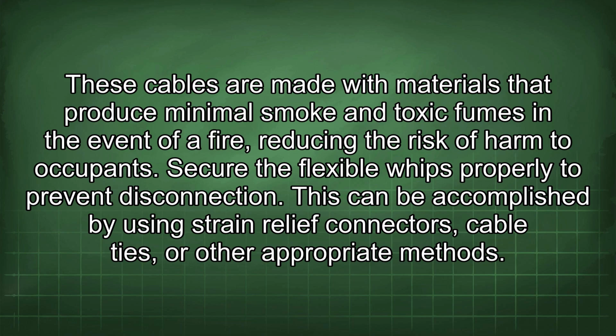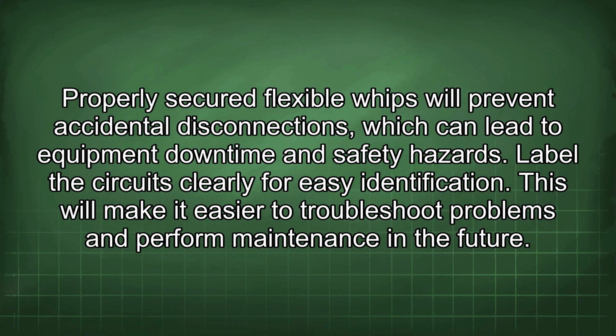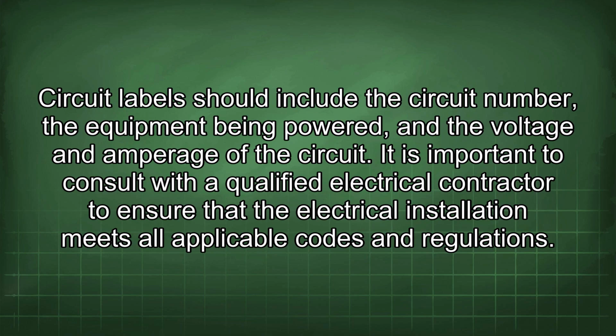Secure the flexible whips properly to prevent disconnection. This can be accomplished by using strain relief connectors, cable ties, or other appropriate methods. Properly secured flexible whips will prevent accidental disconnections, which can lead to equipment downtime and safety hazards. Label the circuits clearly for easy identification. This will make it easier to troubleshoot problems and perform maintenance in the future. Circuit labels should include the circuit number, the equipment being powered, and the voltage and amperage of the circuit.